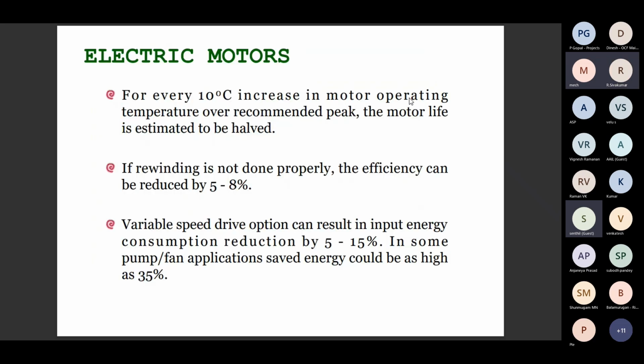Now some energy saving tips for electric motors. For every 10-degree rise in the motor operating temperature over the recommended peak, the motor life is estimated to be halved. You can check it with the thermal meter, which is used in corona temperature testing. The same thermal meter can be used for checking the motor body. As per the specification, every 10-degree rise in temperature will reduce the life of the motor, so it should be monitored very stringently. And if the rewinding is not done properly, the efficiency can be reduced by 5 to 8%.